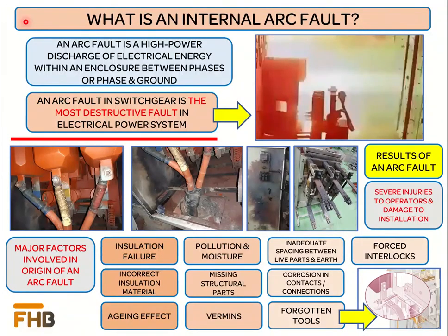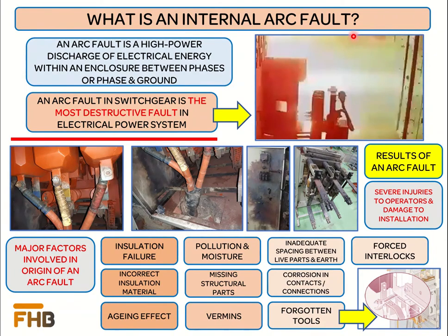What is an internal arc fault? In the simplest form, an arc fault in switchgears is the result of rapid release of energy due to arc travel through ionized air between phases or a phase and ground. In power systems, an internal arc fault is considered the most severe type of fault as its results are quite devastating. If the switchgear installation is non-internal arc proof, this fault can cause severe injuries to operators present in the close vicinity of the affected installation and can also cause damage to nearby installations.